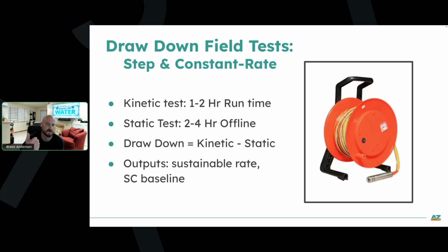But you want to log a couple things. You want to get your kinetic water level, so that's your pump running. So get it to turn on and run for an hour to 2 hours. And what is the water level at just in normal conditions? And then you want to do your static test. Let the well pump sit for, I would say, at least 2 to 4 hours offline and recover, and then check your levels. And then your drawdown is your kinetic level minus your static level.